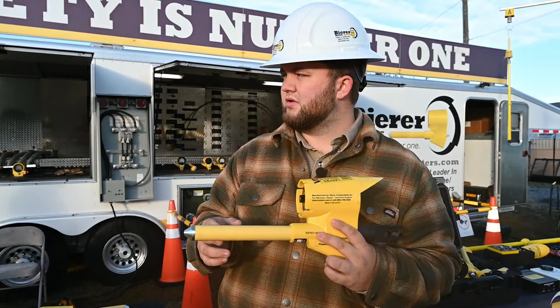But what we do, I think is it OSHA or ASTM? Who recommended that? ASTM. ASTM recommended putting a line limit mark on the probe. So that line limit mark is a recommendation of where you don't want to bypass on this tool with a potential or a potential ground plane. For that same reason, since there's conductive components in here, say you're making contact with a potential at the probe tip and nearby there's another potential or a ground, you start getting close to this meter housing, what you can see is an external flash to those components. A lot of times it's not going to hurt the tool, it's just going to create a path, from either conductor to conductor or conductor to ground. So just improper work methods, Brent will go into more depth on that.